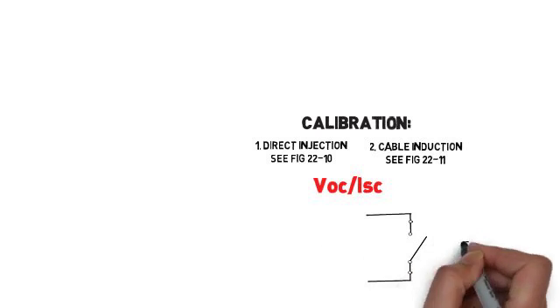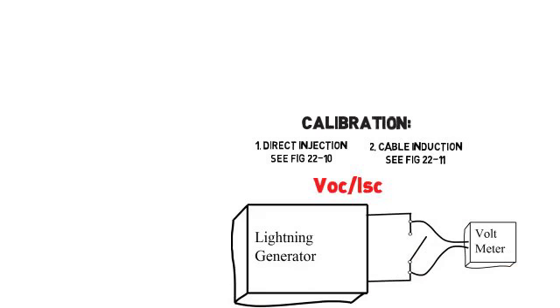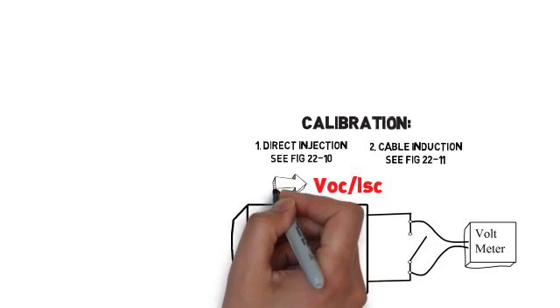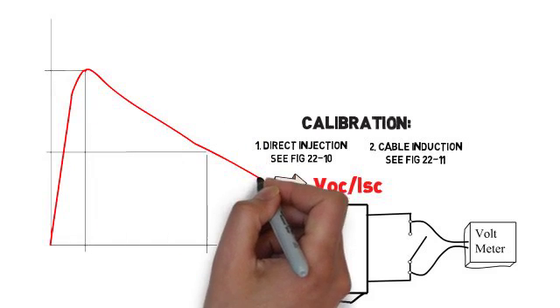First, what you're going to do is put your circuit in the open circuit configuration and ramp up the transient generator until you hit the voltage level specified by your category. Also make sure that your timing requirements for your waveform are correct.